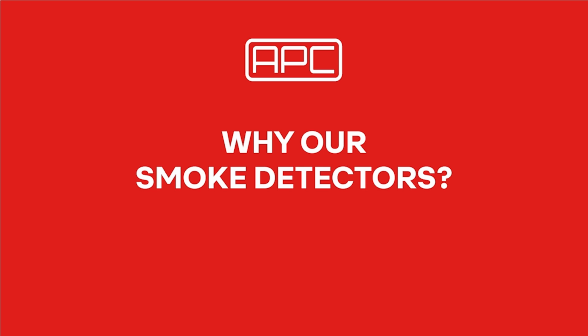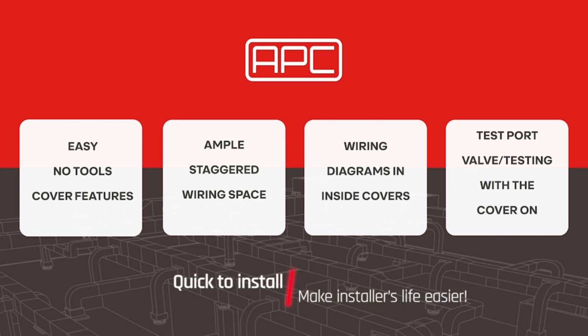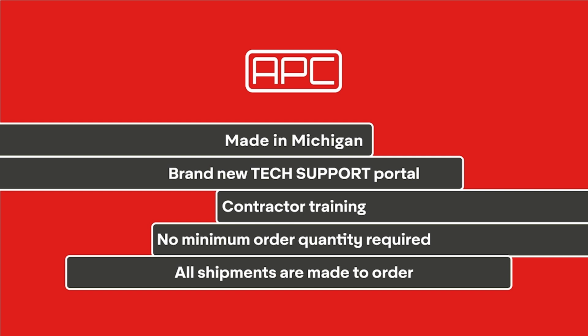Why is Air Products and Controls the better duct smoke detector product line? The detectors are easier to install and maintain. The covers are removed with either 4 screws, 4 thumb screws, or a lever. The staggered wiring or the terminal blocks make the wiring quick and easy. APC is proudly designed, manufactured, and distributed out of our Auburn Hills, Michigan facility. We offer a tech support portal for self-service troubleshooting, contractor training through our local manufacturers reps, no minimum orders, and all of the shipments are made to order.